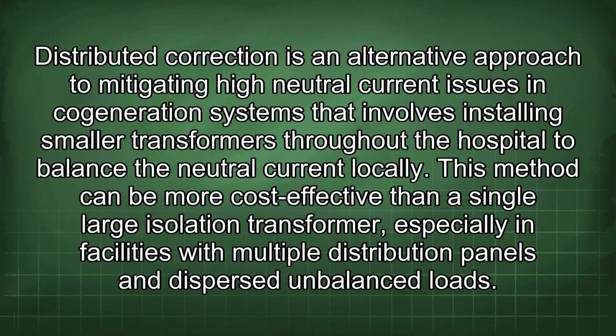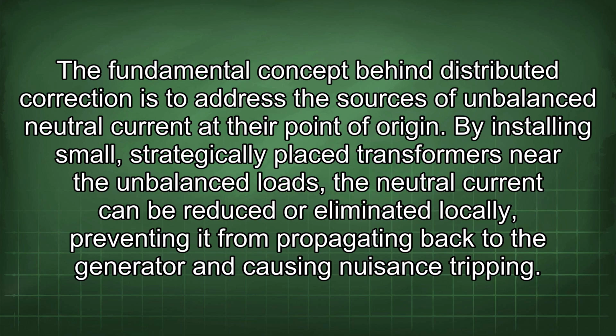Distributed correction is an alternative approach to mitigating high neutral current issues in cogeneration systems that involves installing smaller transformers throughout the hospital to balance the neutral current locally. This method can be more cost-effective than a single large isolation transformer, especially in facilities with multiple distribution panels and dispersed unbalanced loads. The fundamental concept behind distributed correction is to address the sources of unbalanced neutral current at their point of origin. By installing small, strategically placed transformers near the unbalanced loads, the neutral current can be reduced or eliminated locally, preventing it from propagating back to the generator and causing nuisance tripping.